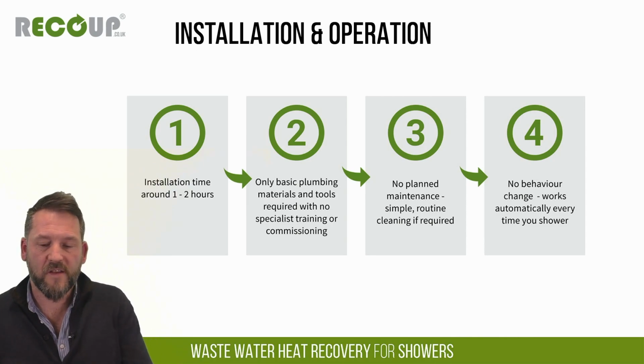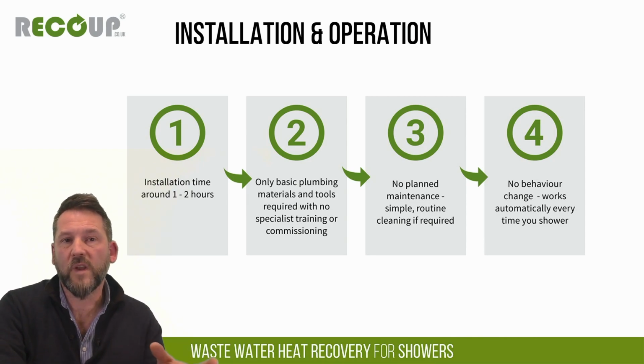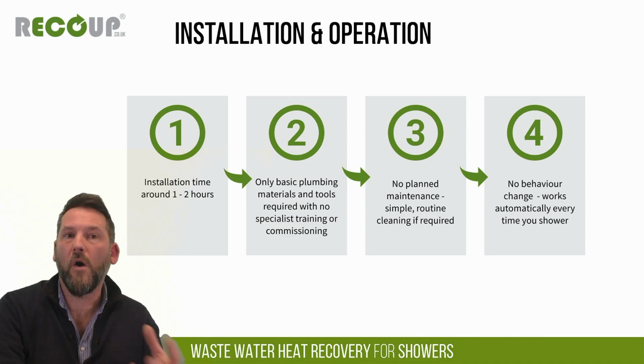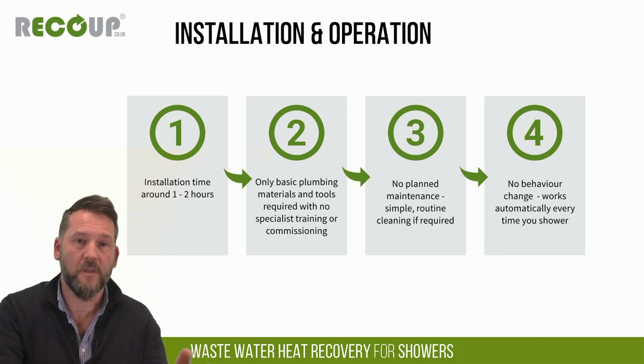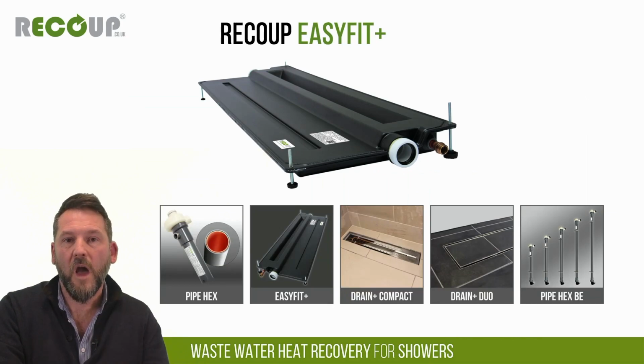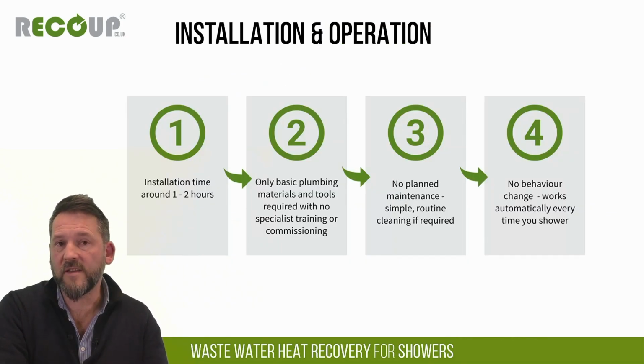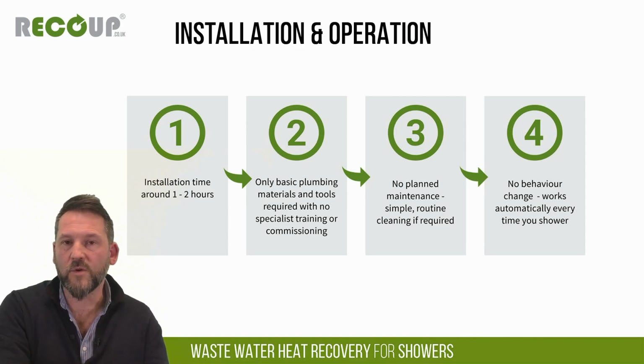Just a quick overview on installation and operation. We've kind of touched on this really, but wastewater heat recovery is generally a first fix installation product, installed around about 1 to 2 hours of extra plumber's time. It really is that simple. Only basic plumbing materials and tools required, so off the shelf isolator valves, etc. Standard tools, no specialist training, no MCS accreditation or certification required, and no commissioning other than the standard pressure testing of the hot water system. No planned maintenance required, as I said earlier, because there's no moving mechanical parts, no filters, no consumables, and importantly, no behavioural changes. So your end user simply won't know it's there in most cases.